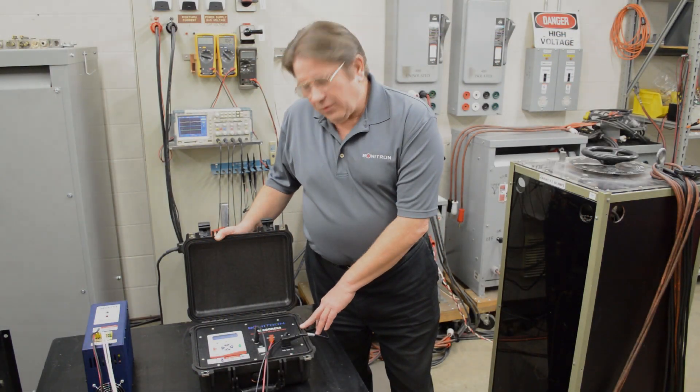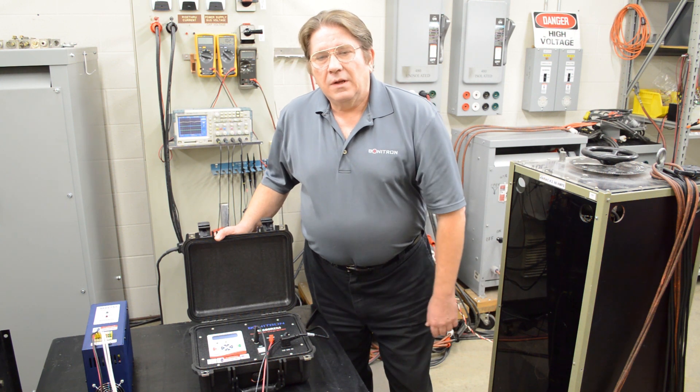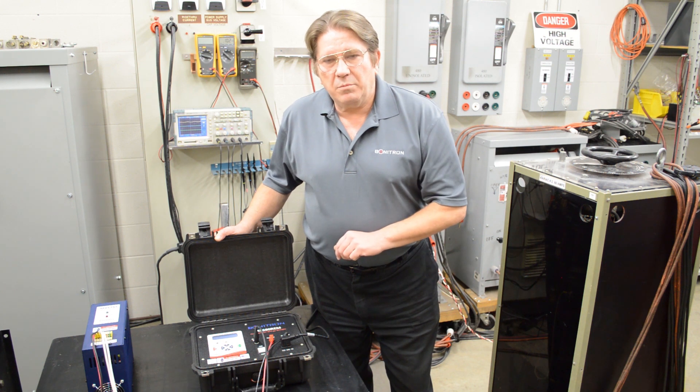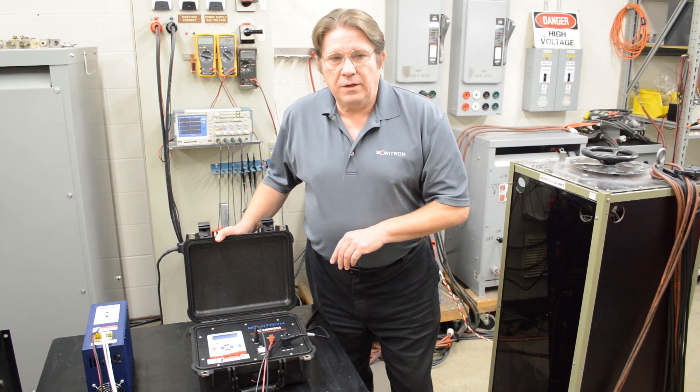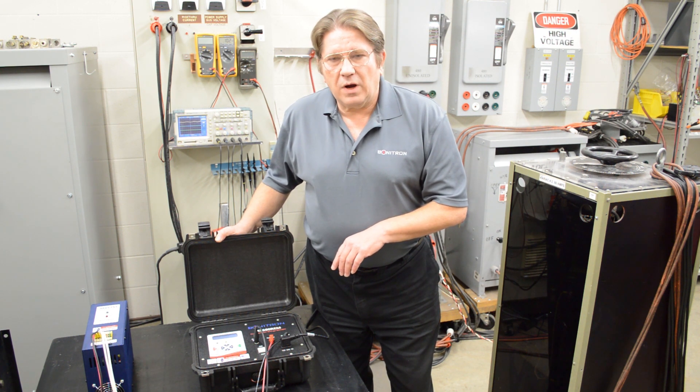Today we are demonstrating the M3660 REM Regen Energy Monitor. The purpose of this is to be able to connect this to an installed drive's DC bus and to be able to monitor the regenerative energy presented during overhauling or deceleration cycles of a drive in a process.